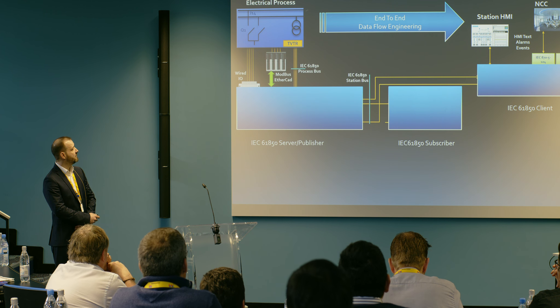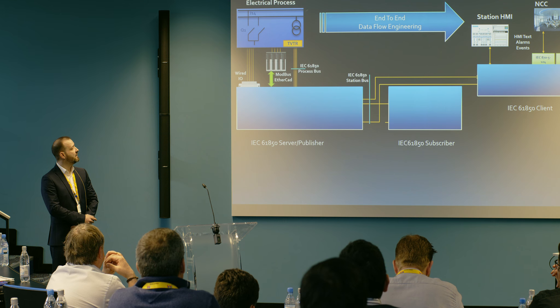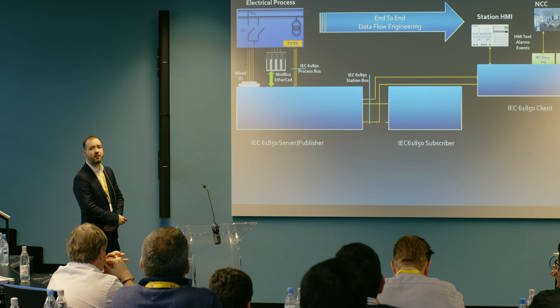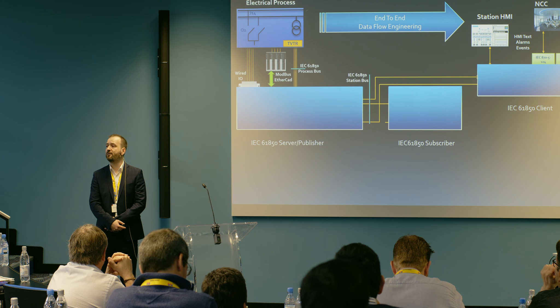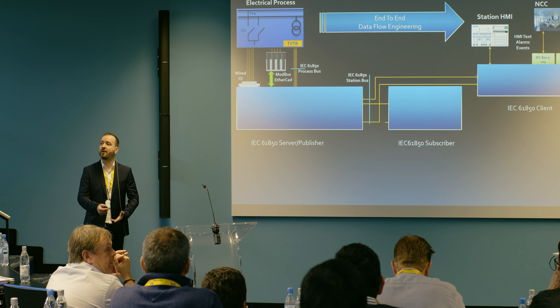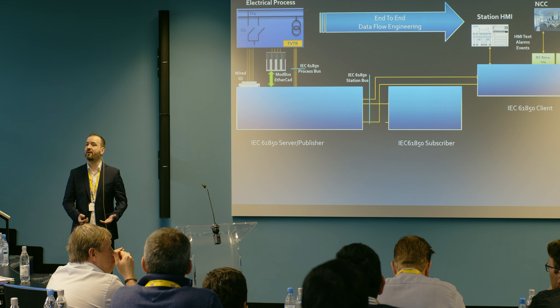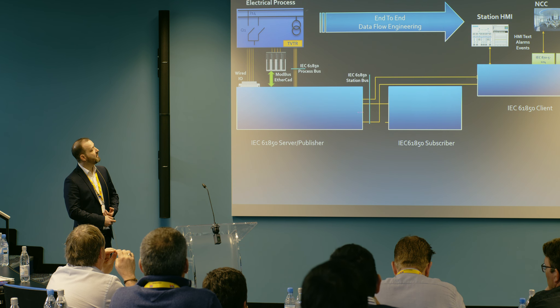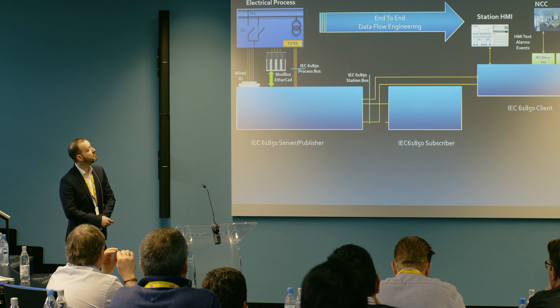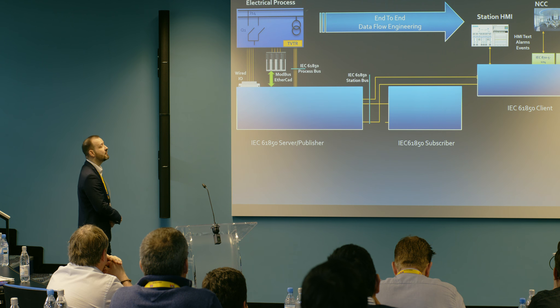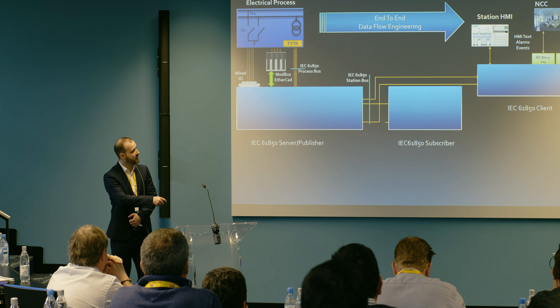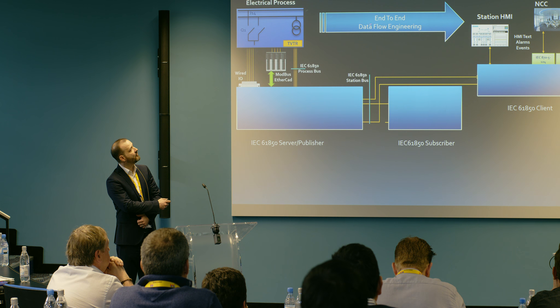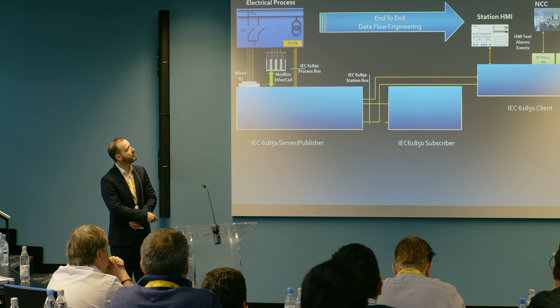When we have the data in an IED acting as a server or publisher, there are several ways IEC 61850 communicates this data. We have reports, GOOSEs, and sample values. With these mechanisms we can go in a horizontal step to other devices on the same level, or we can have vertical communication to a gateway or other client, which finally ends up at the HMI or network control center.